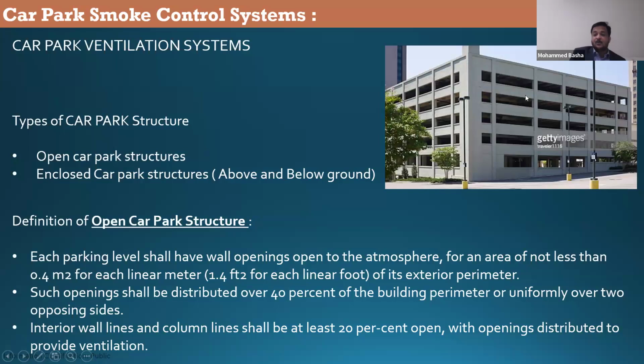By seeing, you can say it's an open car park, but to qualify this as an open car park, some opening sizes must be maintained. Each parking level shall have wall openings open to atmosphere for an area of not less than 0.4 square meter for each linear meter of its exterior perimeter. You need to have such openings. Such openings shall be distributed over 40% of the building perimeter or uniformly over two opposing sides. Why two opposing sides? Because the air from the outside will go into the fire area and will take the smoke out of the other area. That's why the openings shall be distributed at two sides.